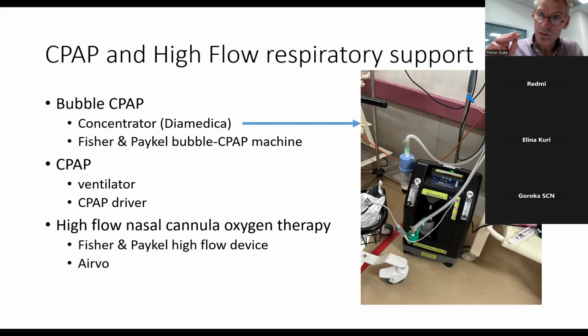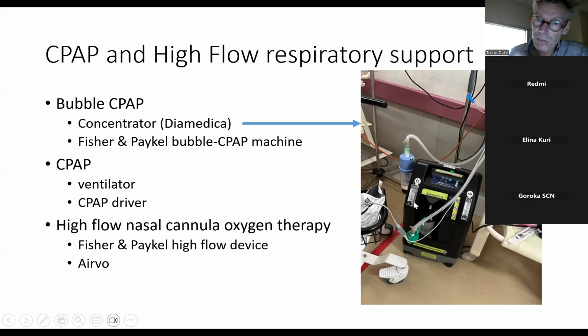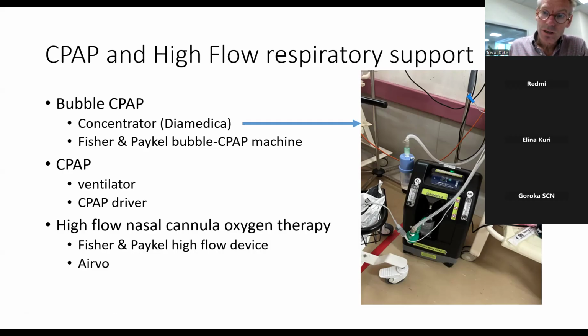In most concentrators, there's usually just one outlet, an oxygen outlet. But in this type of concentrator, they have both an oxygen outlet and an air outlet. The air outlet produces gas flow with a fraction of inspired oxygen the same as air, so 21%. And the oxygen outlet produces gas flow that is the same as what the concentrator does, which is around about 93%.